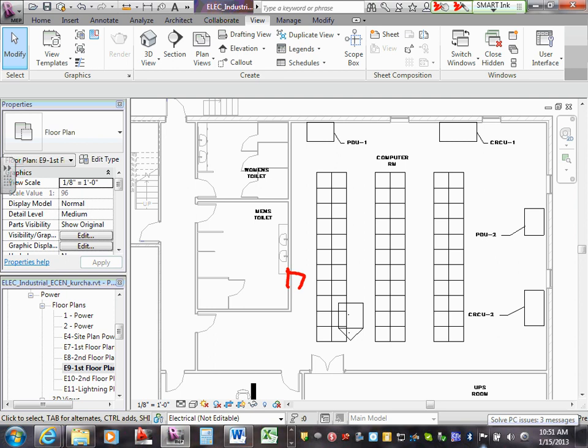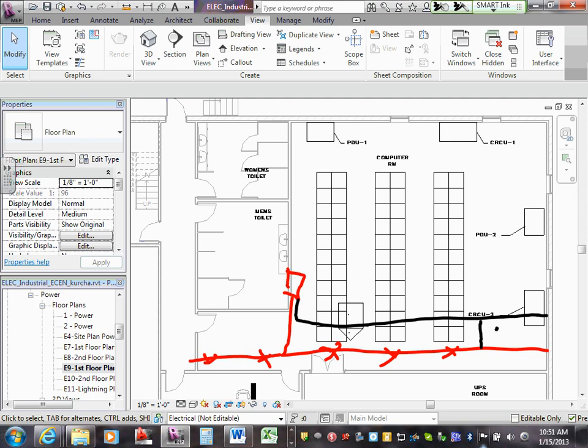All right, you got your controller, your first pipe coming down, going over. The sampling pipes, our tubes, are going to be roughly every 9 feet, all the way across. Your second pipe, which is a separate zone on the system, is going to be 9 feet away, and you're going to have the sampling of the same pipe. Depending on this area, how far it is, so we're at 40 feet, we might be looking at a third or a second system in this area.